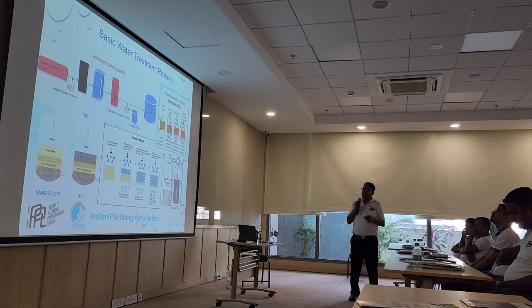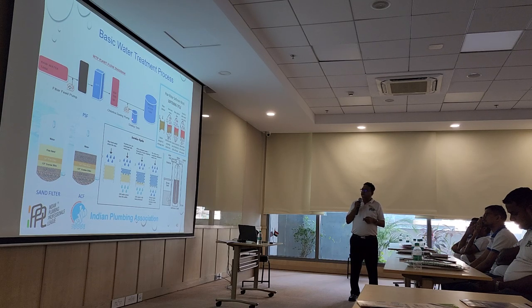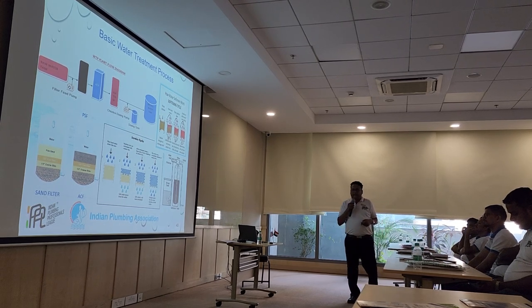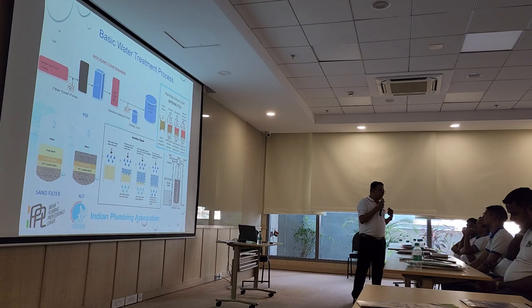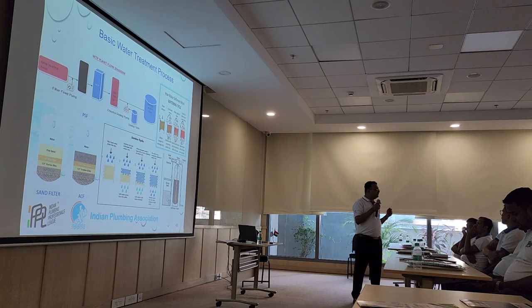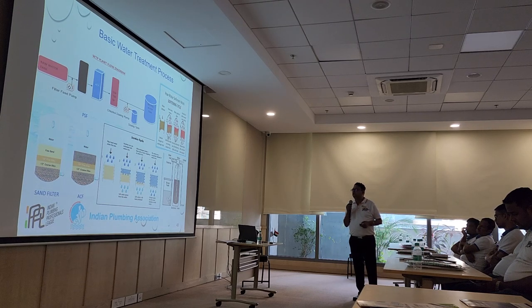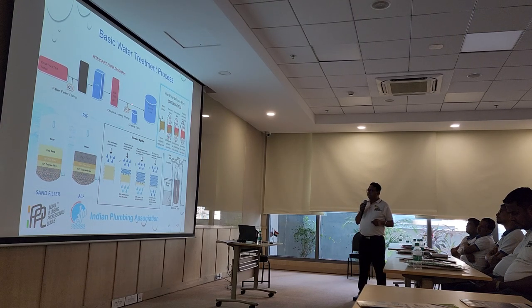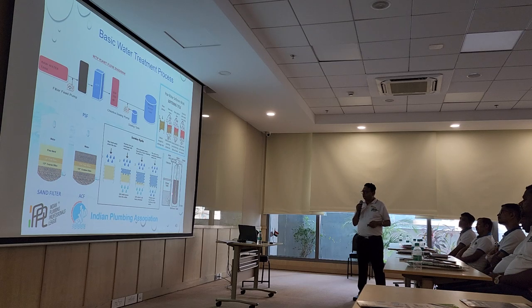The basic water treatment run process: raw water collection, pre-filter pump, activated carbon filter, softener for different hardness levels, then dosing tank, chlorine dosing pump, and treated water. Water treatment is quite straightforward compared to sewage treatment. There is also a softening cycle with a service cycle and a brine tank which adds brine solution to make the water soft.